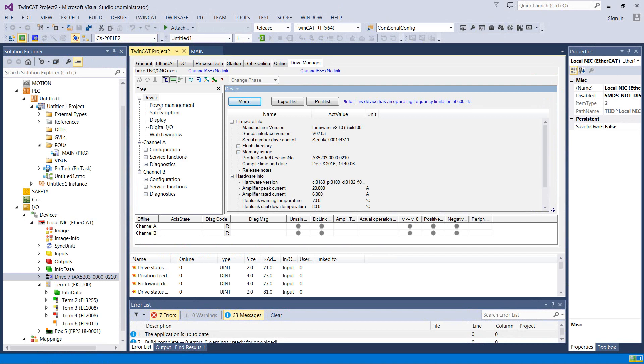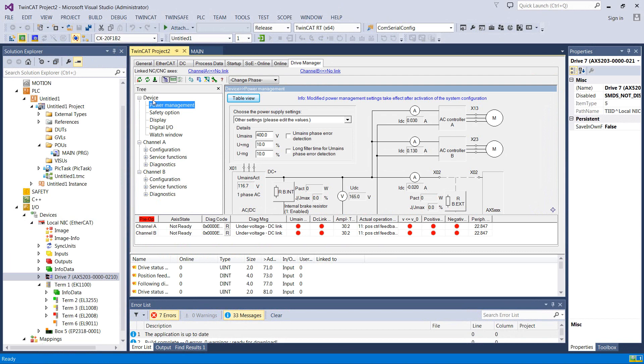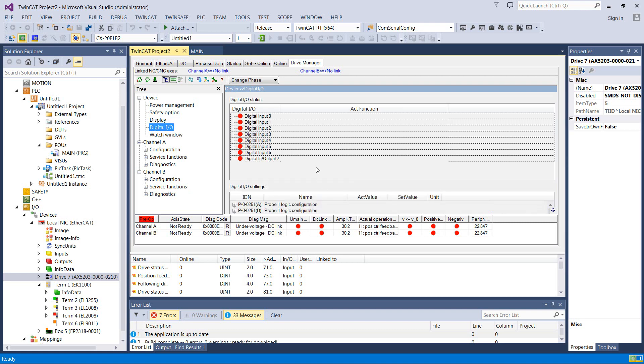And this is the drive manager. We've got channel A, channel B. Those two are identical except that one is for one of the servos and the other is for the other one, right? So device here is going to be everything that's common to the drive itself, the digital I.O., stuff like that. So let's find out what it's upset about right now, and you can find that quickly down here in this diagnostic code.